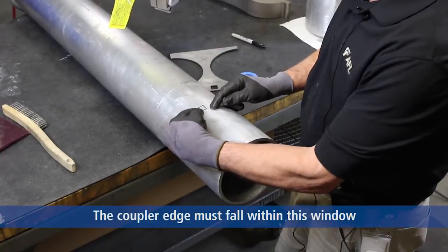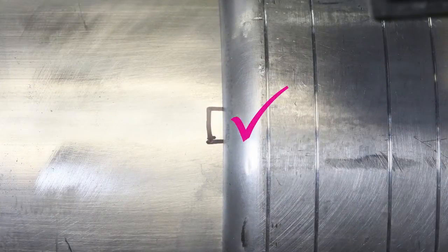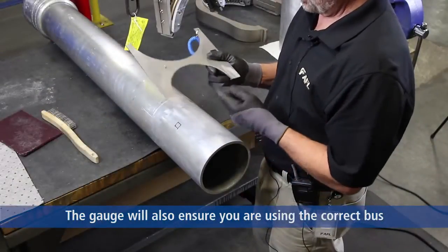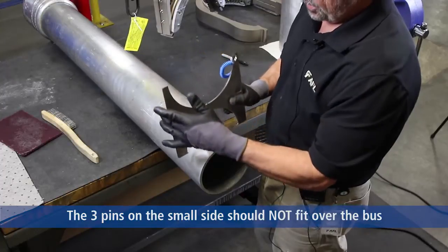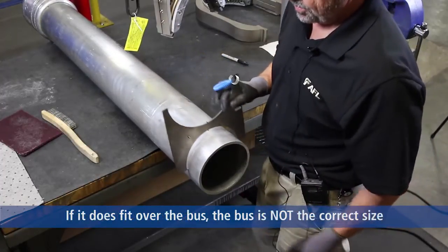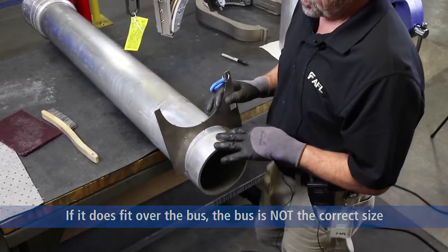The reason we do this marking with the coupler is to prevent two pieces of bus from touching once they're inside of the coupler, which gives you a flexing and sweeping motion in your bus. The small side of the gauge has three pins on it. Place the gauge over the bus and it will not fit. If it does fit, then you probably have an off-size piece of bus.